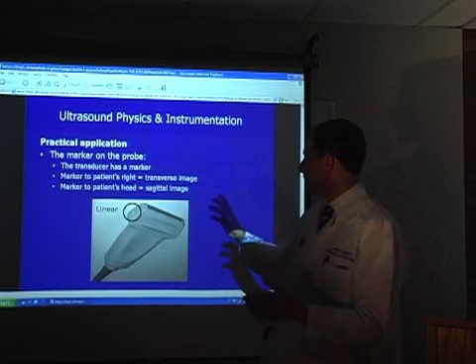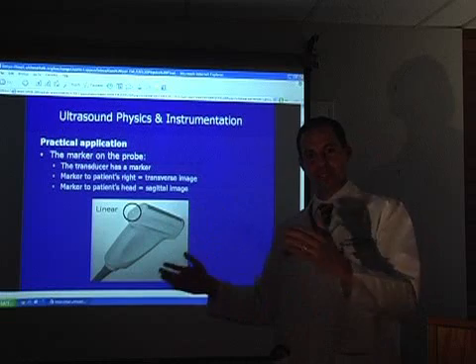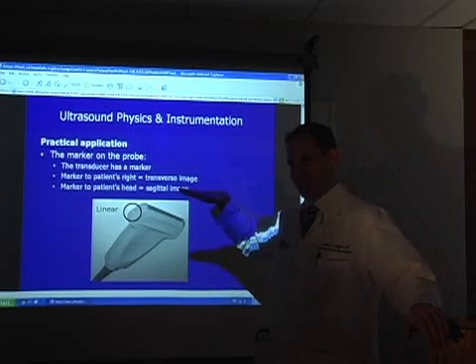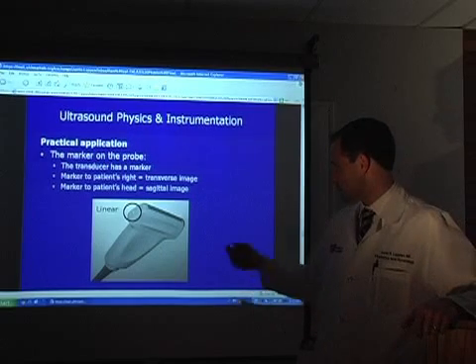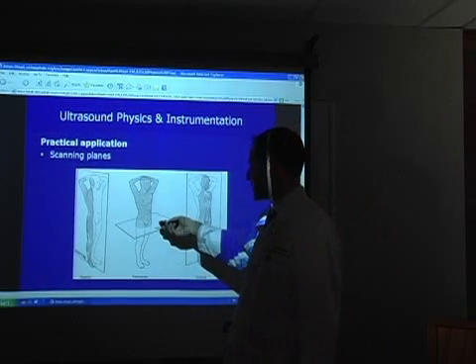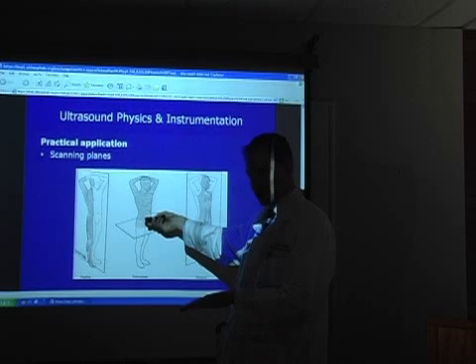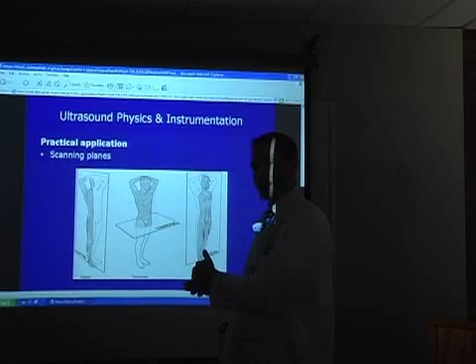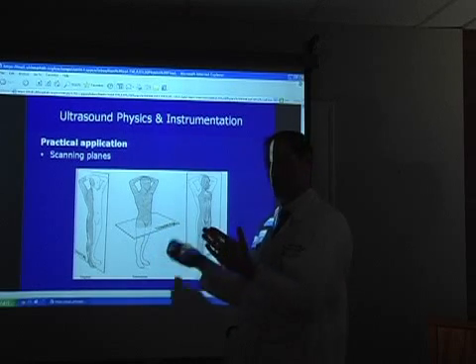If you're scanning a patient in the transverse plane, that marker is going to be to the patient's right — or it could be to the patient's left — but you have to know which side of the image on the screen you're looking at. It's about which way you're holding the probe: are you holding it to produce a transverse image or a longitudinal image? The notch side is critical because that's what correlates with what you see on the screen.